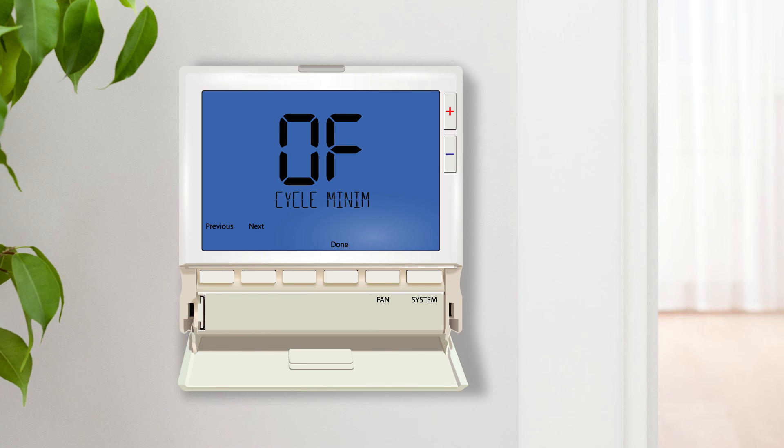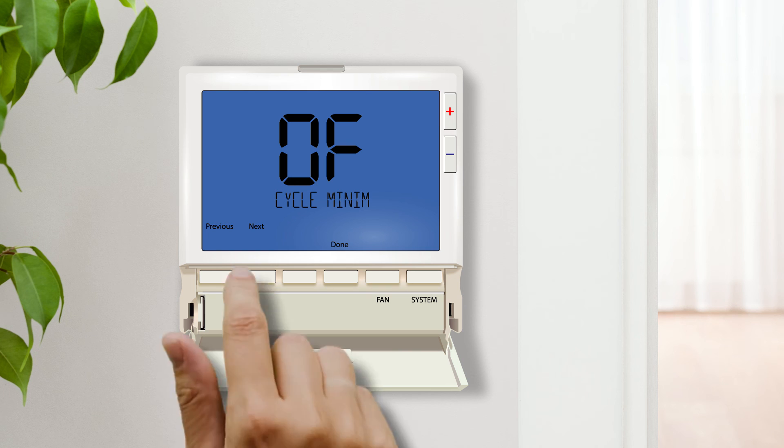Cycle minimizer maximizes efficiency and equipment longevity by increasing the heating and cooling swing setting to 2 degrees during the unoccupied and leave time periods. The feature is only available if programming is on.